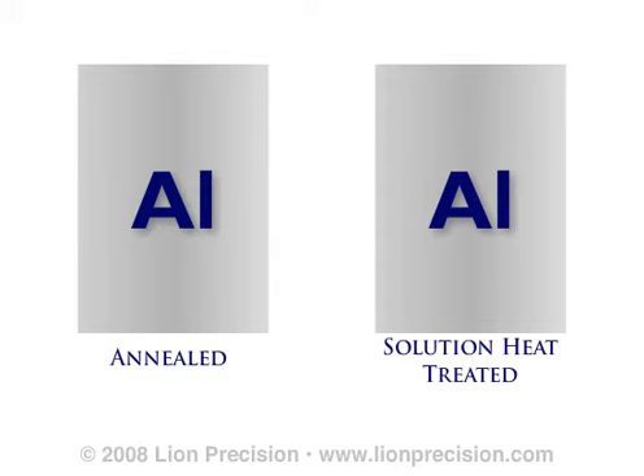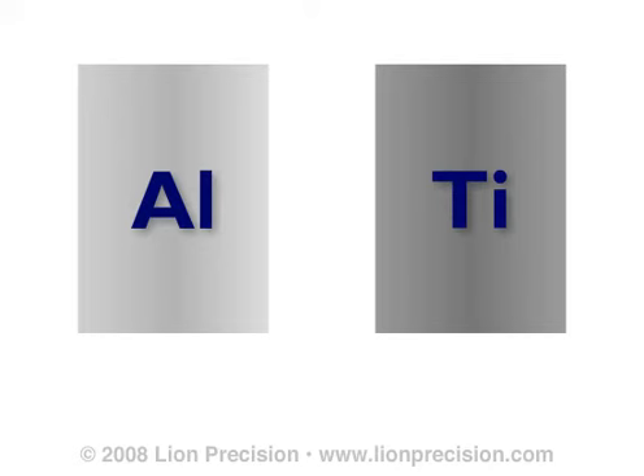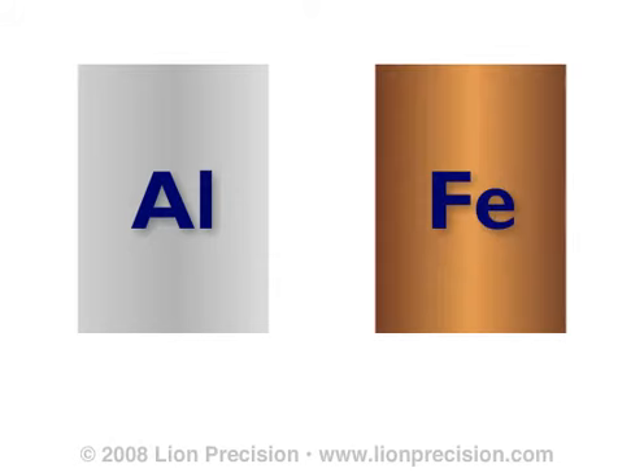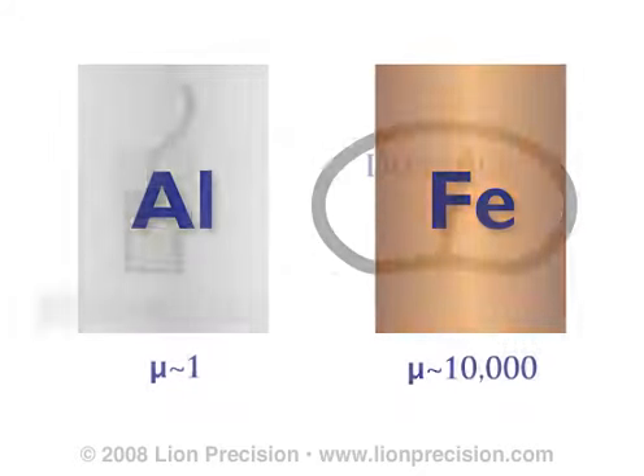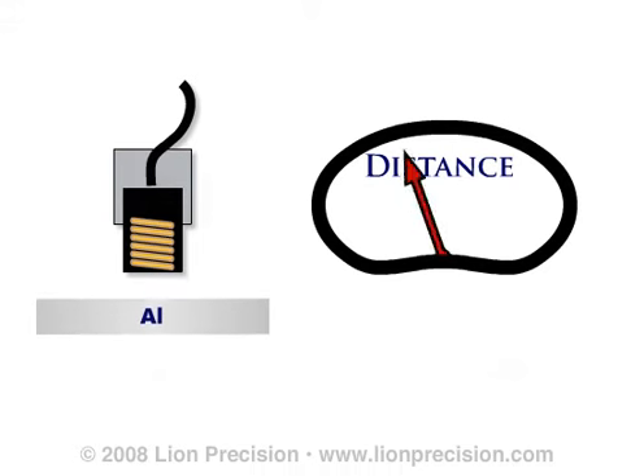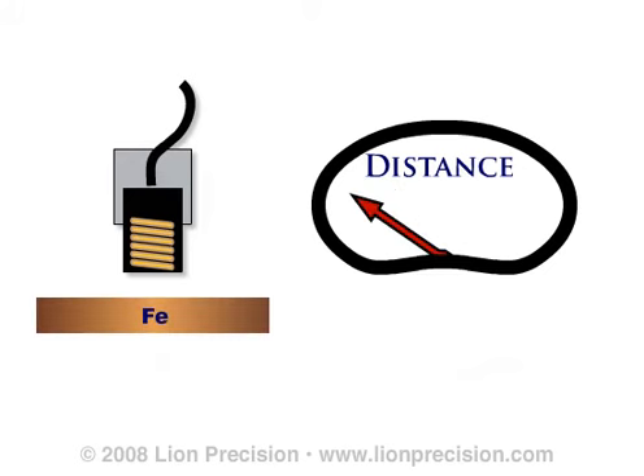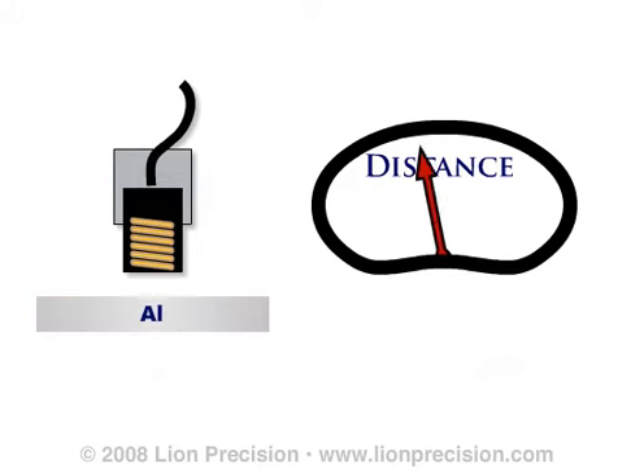Between different non-magnetic materials, such as aluminum and titanium, the variance of permeability and resistivity can be small. But a high-performance eddy current sensor, calibrated for one non-magnetic material, will still produce errors when used with a different non-magnetic material. The difference between non-magnetic materials and magnetic materials, such as iron or steel, are enormous. While the relative permeability of aluminum and titanium are approximately 1, the relative permeability of iron can be as high as 10,000. Eddy current sensors calibrated for non-magnetic materials are not likely to function at all when used with magnetic materials.